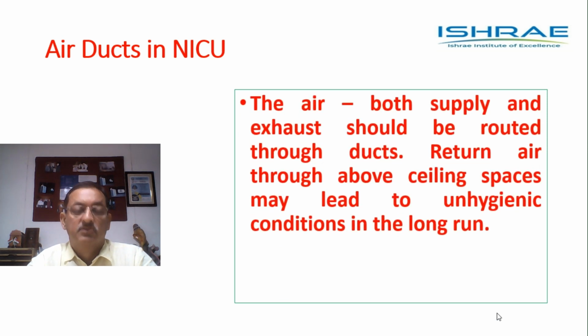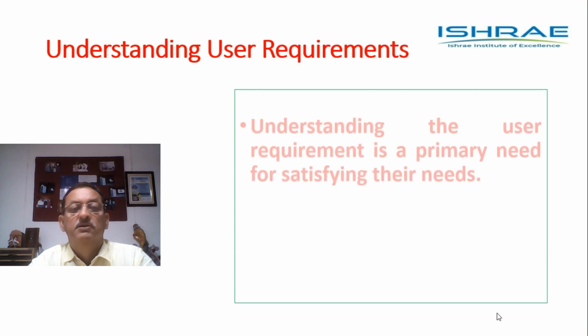Air ducts. This is also something that I need to talk to you about. The air, both supply and exhaust, should be routed through ducts. Very often in air conditioned spaces, we allow the return air to travel through the spaces above the ceiling. In the long run, there could be a lot of dust and rodents there, and the air traveling through those spaces will turn out to be unhygienic. We should not allow that to happen, and the air inside a hospital must always travel through ducts.